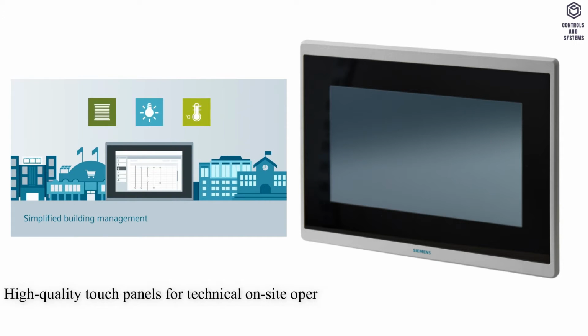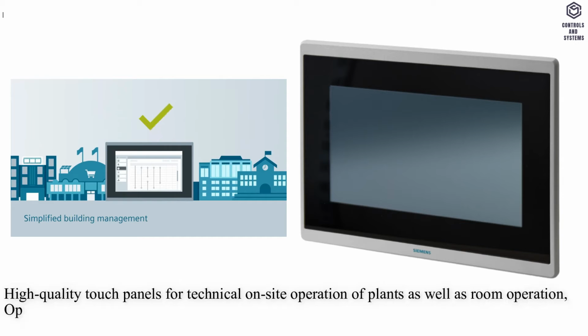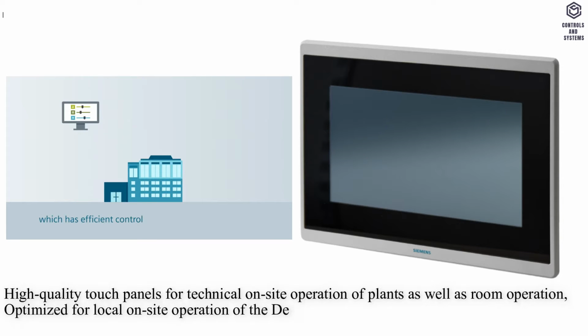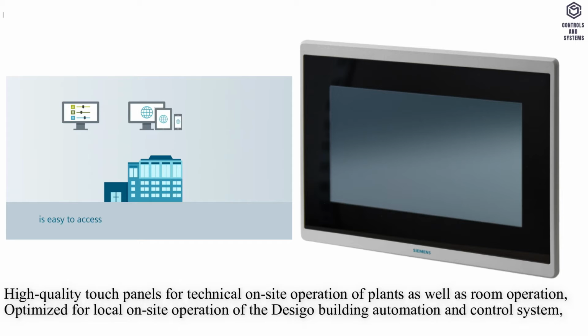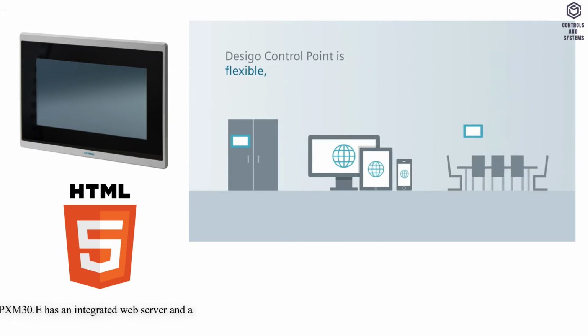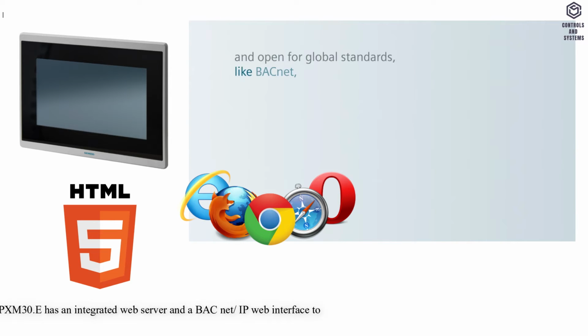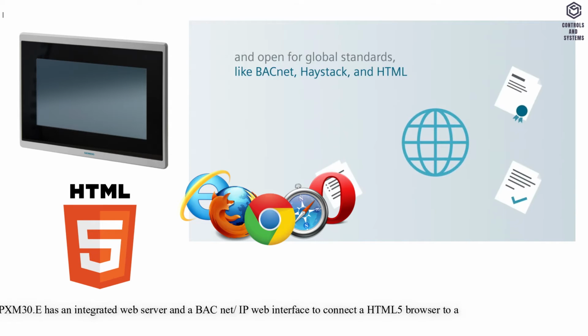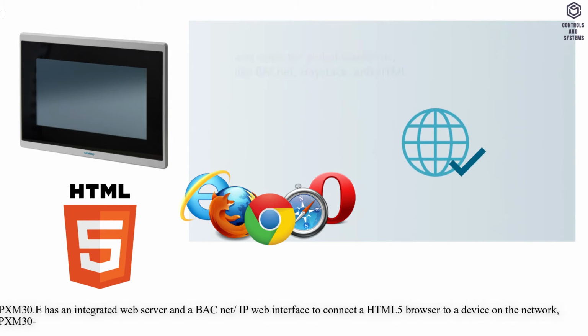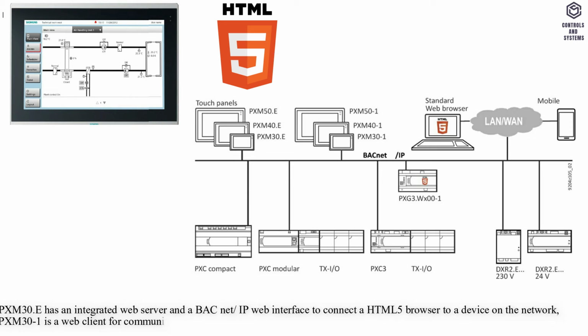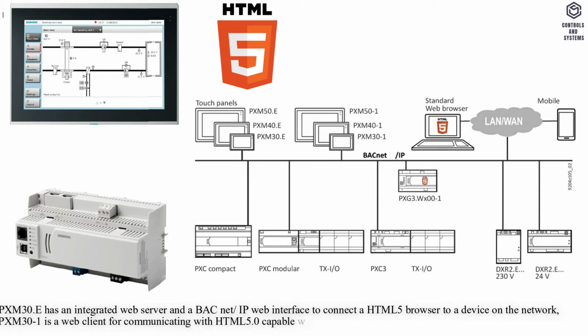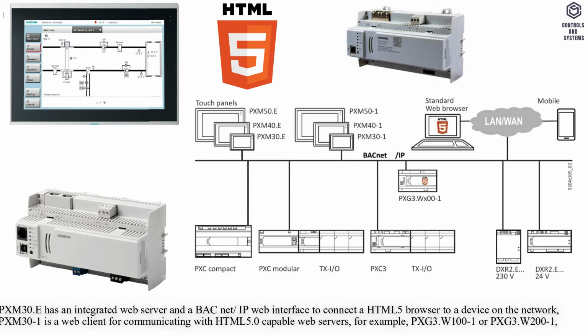Overview. High-quality touch panels for technical on-site operation of plants as well as room operation. Optimized for local on-site operation of the Desigo building automation and control system. PXM 30.E has an integrated web server and a BACnet/IP web interface to connect an HTML5 browser to a device on the network.